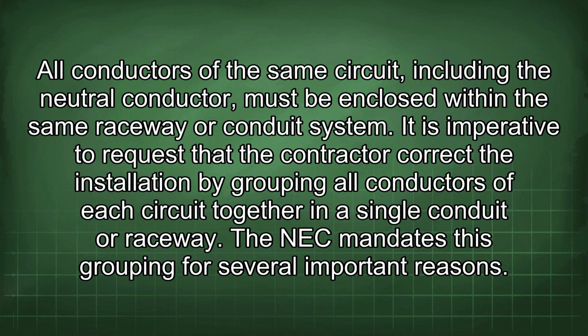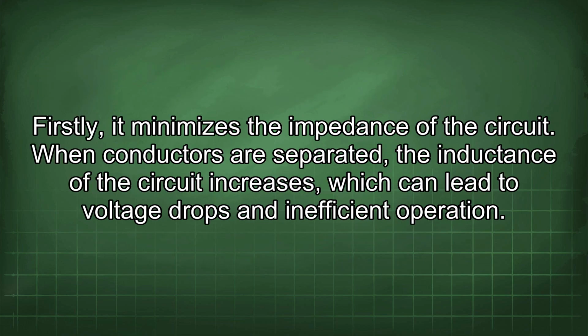All conductors of the same circuit, including the neutral conductor, must be enclosed within the same raceway or conduit system. It is imperative to request that the contractor correct the installation by grouping all conductors of each circuit together in a single conduit or raceway. The NEC mandates this grouping for several important reasons. Firstly, it minimizes the impedance of the circuit.